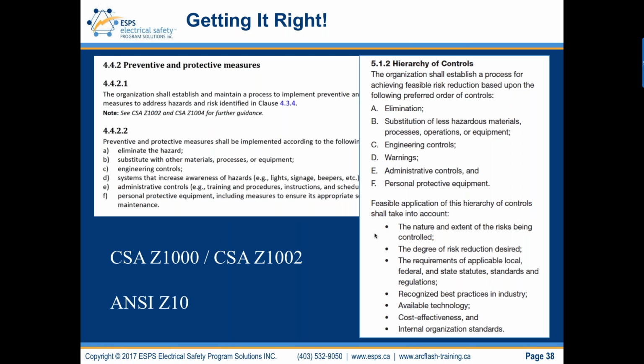But guess what industry's been doing? We've been doing bottom-up for arc flash and shock, which means we bought PPE, we gave it to the workers, we sent them on training, and then it must be happening. And that's the problem. Without an electrical safety program, applying the controls from a bottom-up approach doesn't achieve the results at all. What we do need to discuss is eliminating the hazard as a priority, turning off energized electrical equipment before we do work on it, specifically repair and alteration. We do need diagnostics and troubleshooting in an energized state.